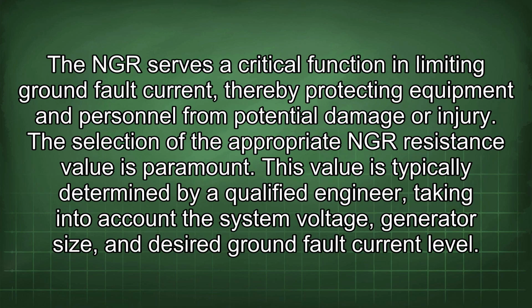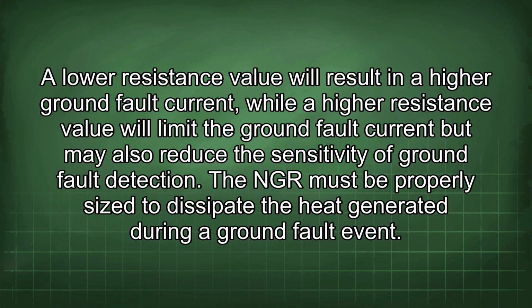The NGR serves a critical function in limiting ground fault current, thereby protecting equipment and personnel from potential damage or injury. The selection of the appropriate NGR resistance value is paramount. This value is typically determined by a qualified engineer, taking into account the system voltage, generator size, and desired ground fault current level. A lower resistance value will result in a higher ground fault current, while a higher resistance value will limit the ground fault current but may also reduce the sensitivity of ground fault detection.